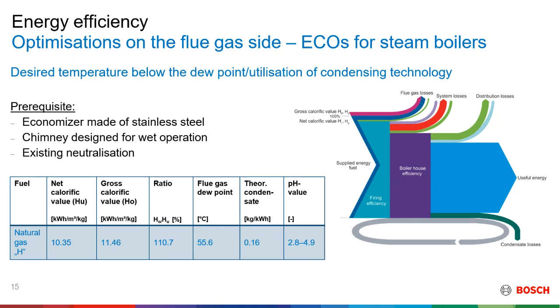How do you avoid it? Usually any fuel will have a dew point, where ideally for, let's say, 2% would be around 130 degrees. So how do you avoid sulfur formation or sulfur dioxide formation in the economizer?